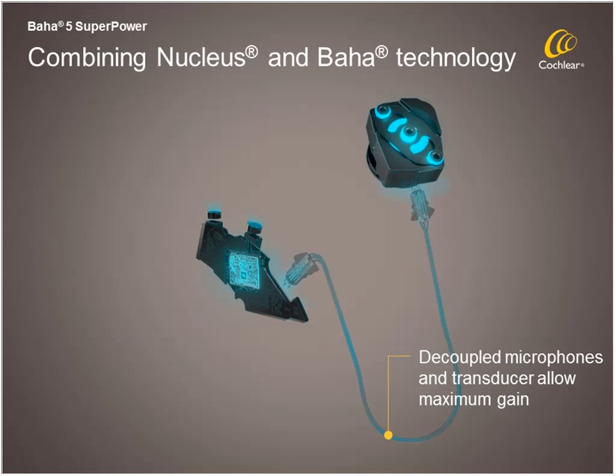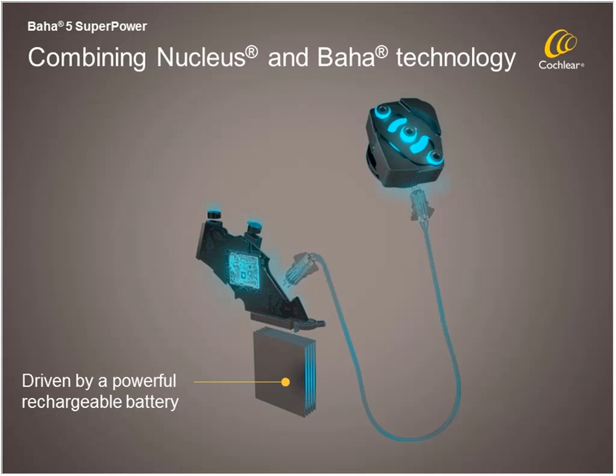So when we get this much power in order to have this much output for 65 dB, we have to separate the microphones and the transducers. The microphones are on the processor itself in the same placement as with our Nucleus 6 product, and then the transducer is separate. Because they are separated, you're not going to have the feedback that you would if they were together. Because it requires so much power for such a 65 dB loss, they use the same rechargeable batteries that our N6 recipients use, and it hooks into the bottom just like the N6 rechargeable battery does.